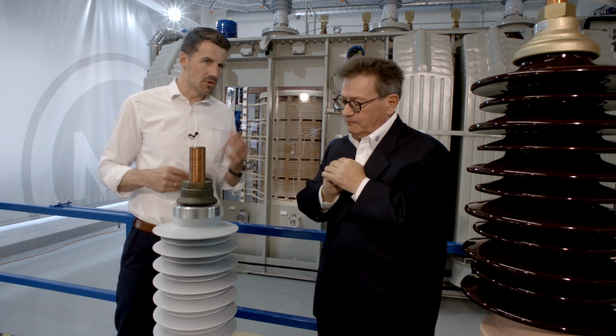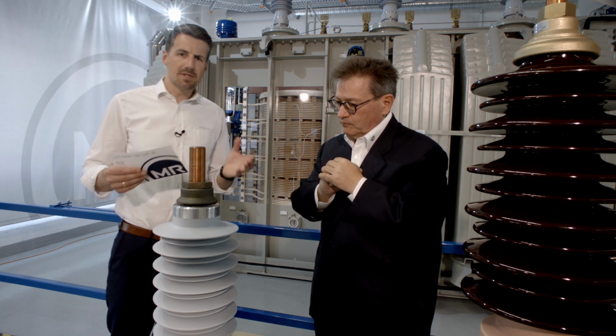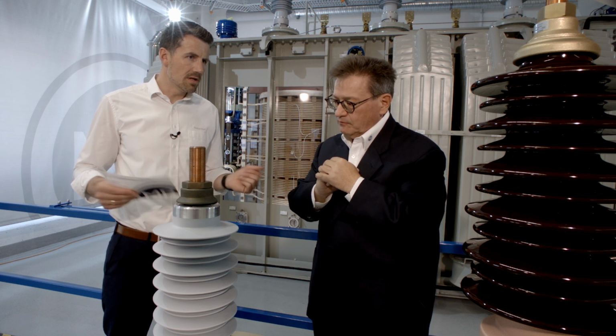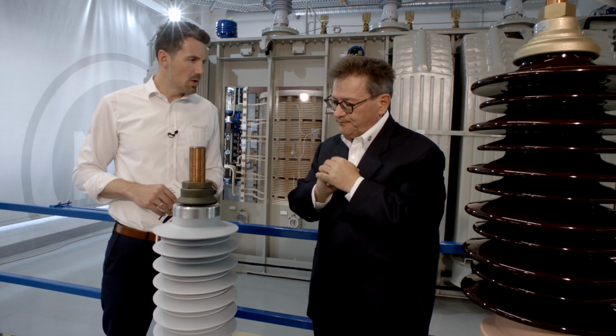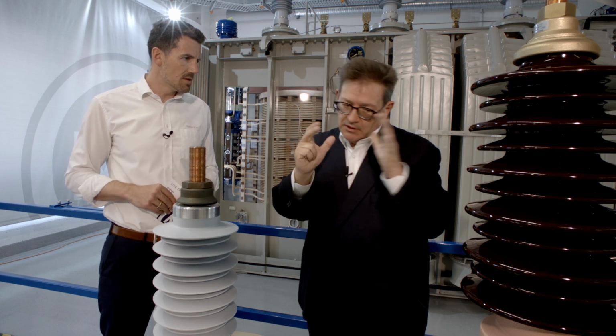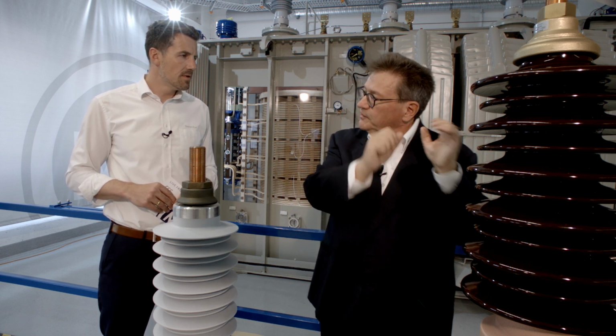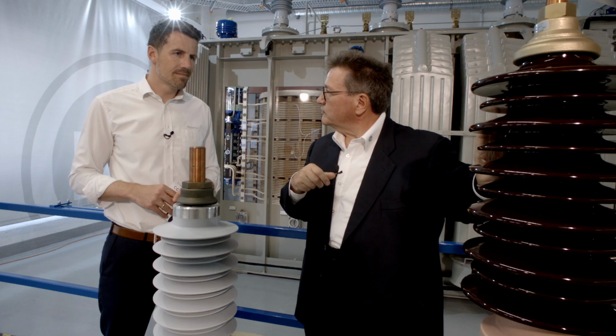Just talking about lead times or delivery times, our customers out there may ask, how long is the typical lead time of a porcelain bushing and of a polymeric one from CEDASPE? What would you say? CEDASPE is not producing porcelain insulators. We source the porcelain insulators from porcelain insulator manufacturers worldwide. This technology is becoming quite old, difficult to automatize, and the labor cost content is quite high. So here we have a quite long lead time due to the porcelain insulator sourcing.